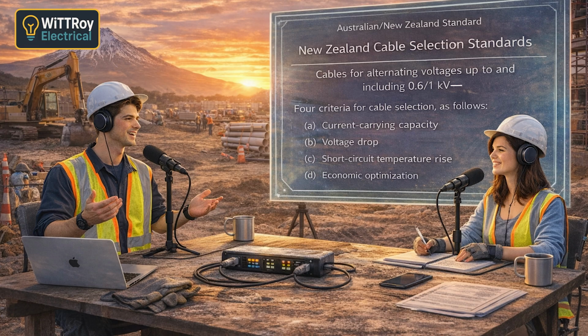Correct. So do we always calculate this? Not always in simple jobs, but important for larger systems. So if the cable is too small, it could be damaged during a fault. Exactly. Okay, that makes sense. Now, the last part, just briefly, is economic selection. Cost. Yes, so small cable is cheaper up front, but wastes more energy over time. And big cable costs more but is more efficient. Exactly. So engineers might choose a bigger cable for long-term savings. Yes, but for exams, we focus more on safety.